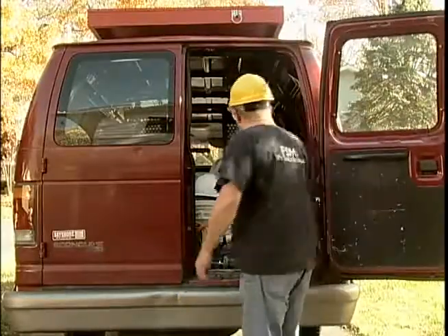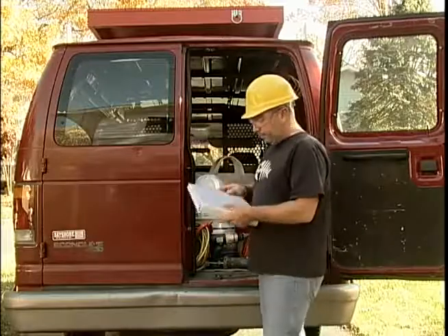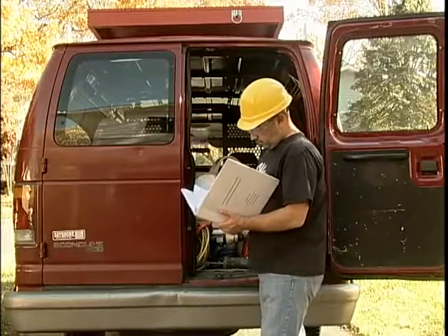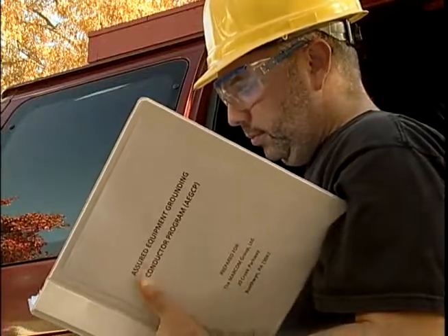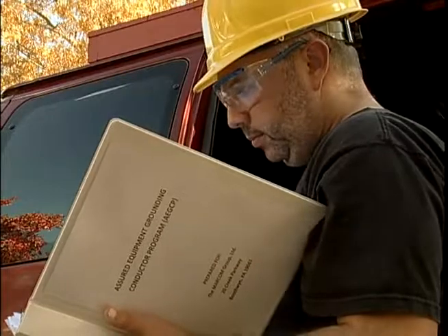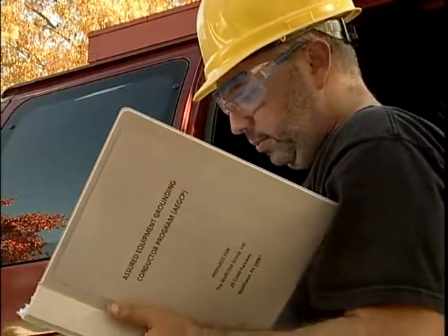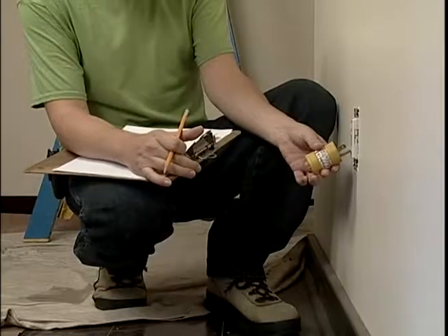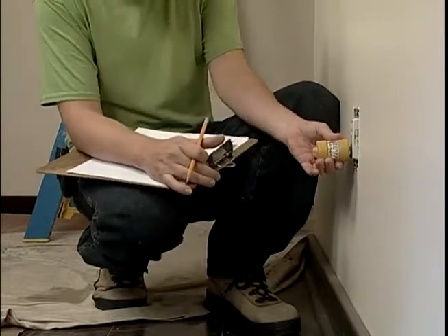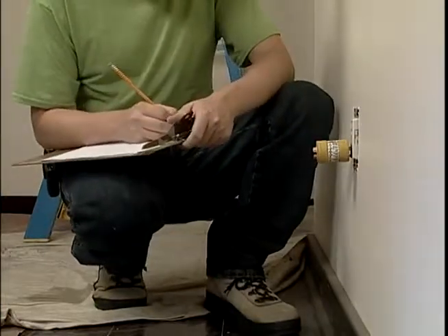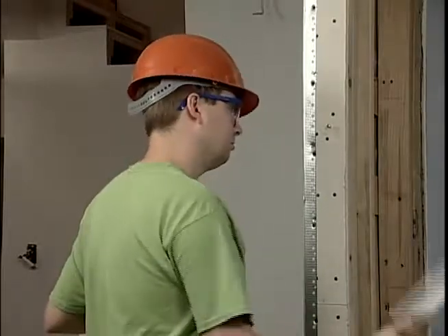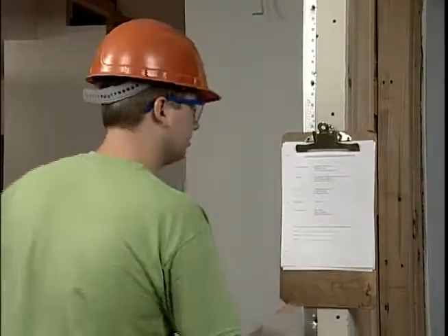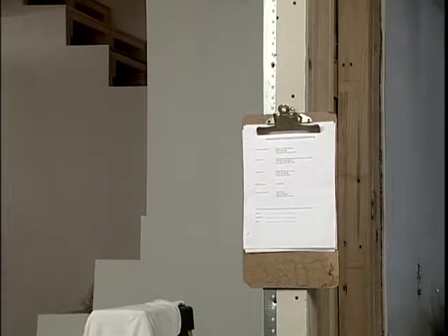OSHA requires that a written description of the AEGCP be kept at the job site. It should outline the specific procedures that have been adopted, including those for conducting the equipment inspections and tests that OSHA mandates. Test schedules should also be documented. All tests must be recorded, and the records must be maintained until the next set of tests is conducted and new records are created. The written AEGCP description and test records must be made available at the job site, to any employee who is working on the site, as well as to OSHA personnel.